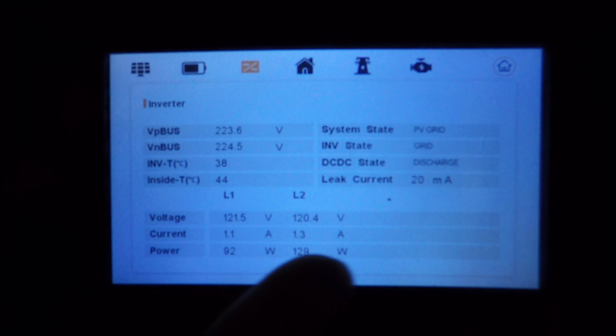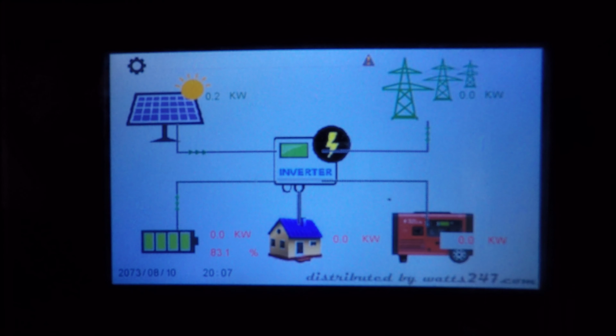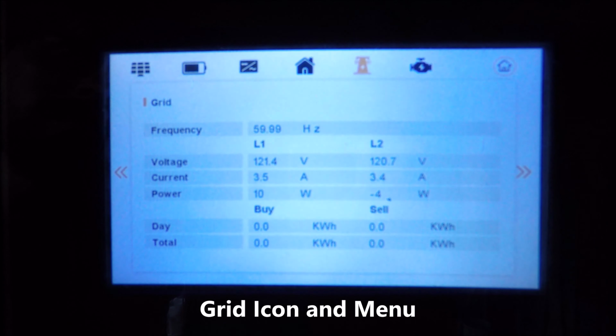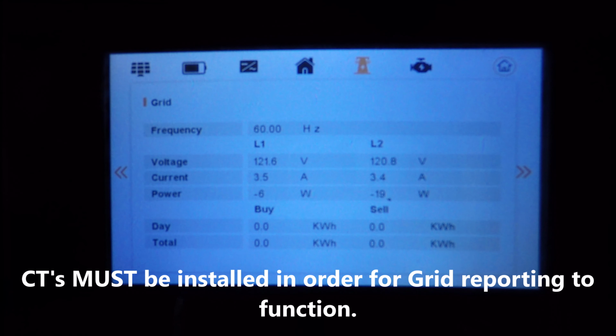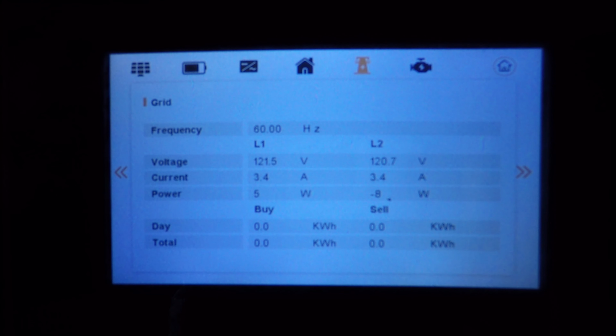L1 is at 120 volts, L2 is at 120 volts. We're pulling about 1 amp on both and about 100 watts from each side. We can look at the grid supply. So our grid frequency is exactly 60 Hertz. Coming in from the grid on L1 we have 121.4, L2 we have 120.7 volts. You can see that our draw from the grid is 3.5, 3.4 amps per leg, and we're using a little bit of 20 watts or so on each leg. And no totals for the day.